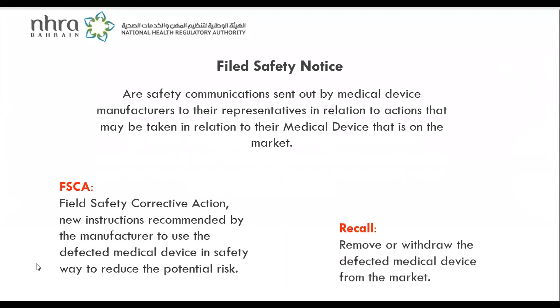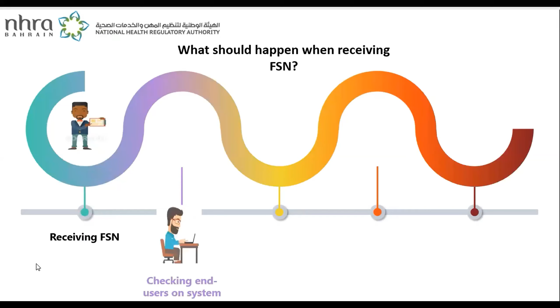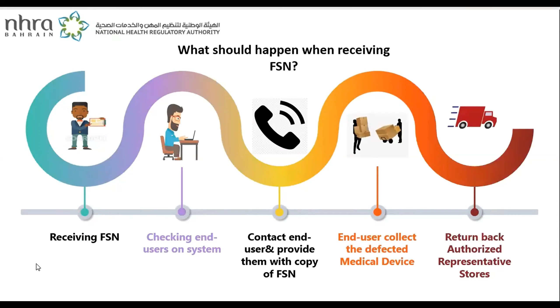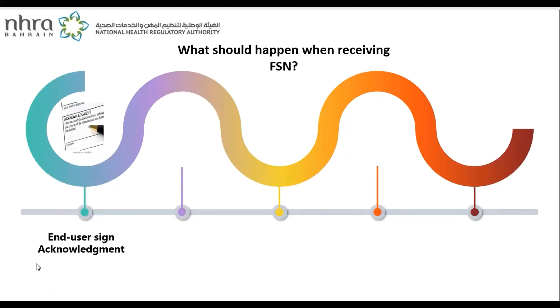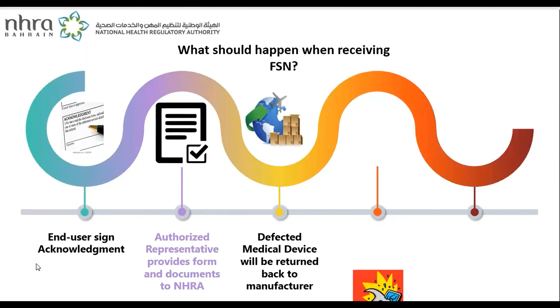Now, what should you do when you receive a field safety notice? This is a scenario to show you what to do when you receive a recall from the manufacturer. Once you receive a field safety notice from the manufacturer, you check the end user on your system, then contact them to take the necessary action according to the field safety notice. The end user will collect the defective medical device and return it back to the authorized representative stores. Then the end user should sign an acknowledgement and provide it to the authorized representative. The authorized representative should provide the form and documents to NHRA. Then the defective medical device will be returned back to the manufacturer or destroyed in Bahrain. Then evidence should be provided, which is an airway bill or invoice of destruction.